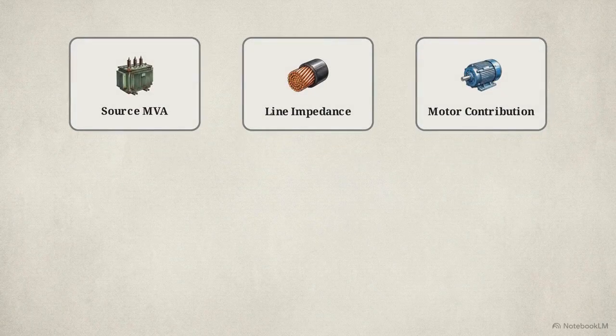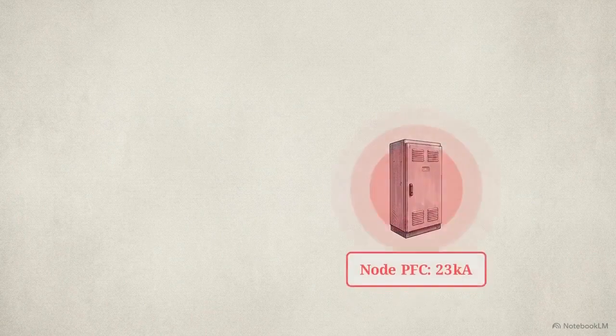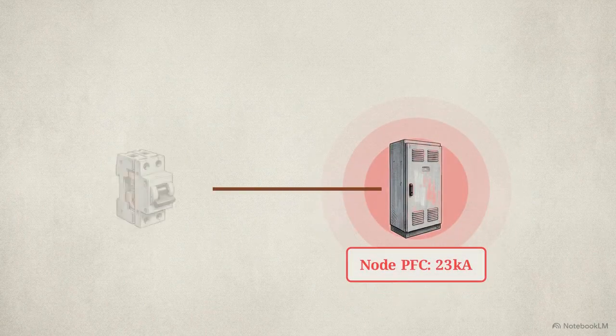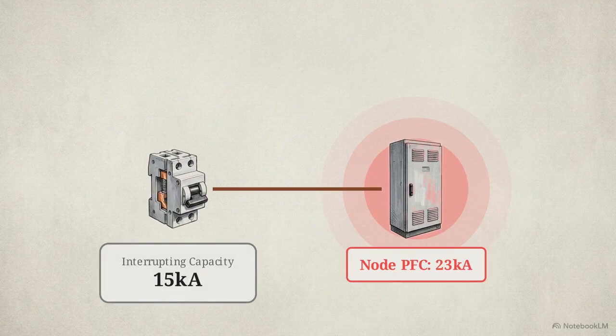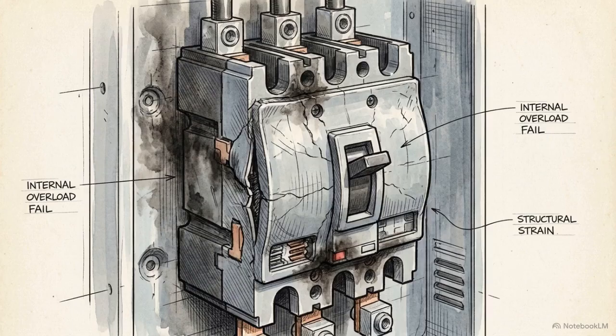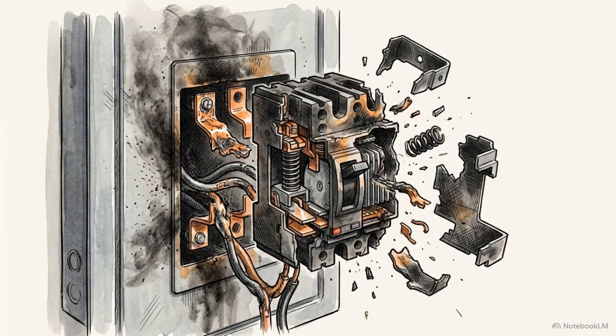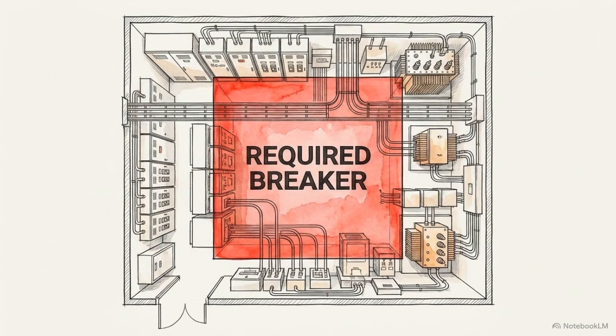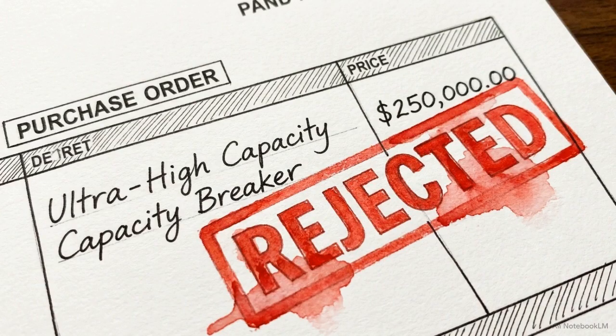Our entire calculation sequence, the source capacity, the line impedance, and the motor contribution, distills down into a single concrete node PFC value. We then place a protective circuit breaker at that specific node. That breaker carries a specific interrupting capacity, rated in kiloamperes. For the system to be safe, that breaker's capacity rating must physically exceed the node's maximum calculated current. If the interrupting rating is lower than the PFC, the breaker is incapable of clearing the fault without tearing itself apart. But an unavoidable problem arises when the mathematically required breaker rating is too massive, excessively expensive, or physically impossible to install in the facility.